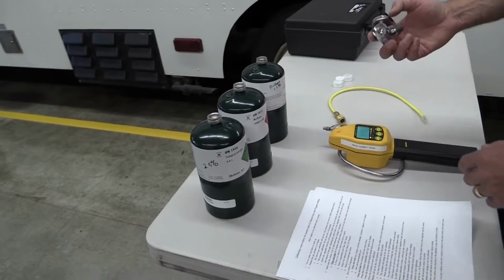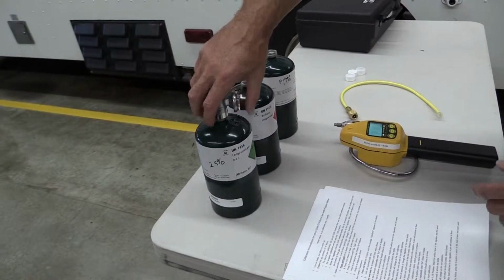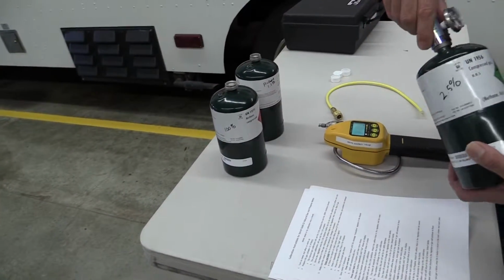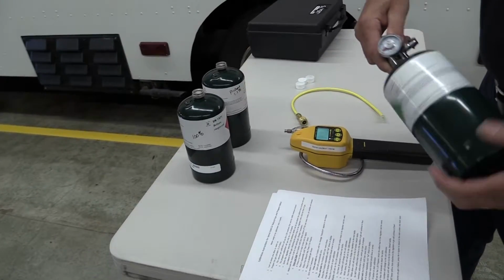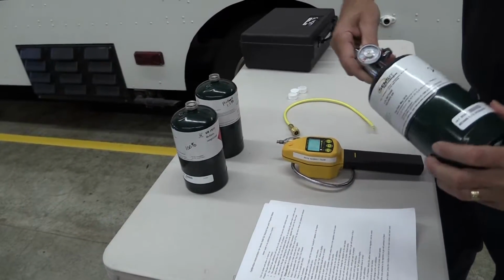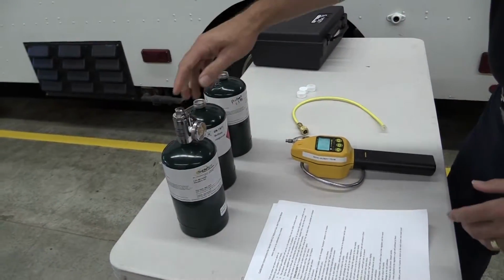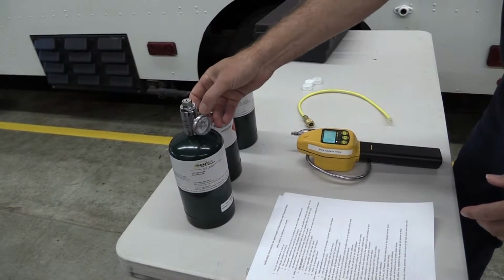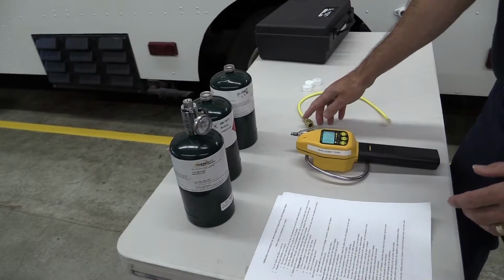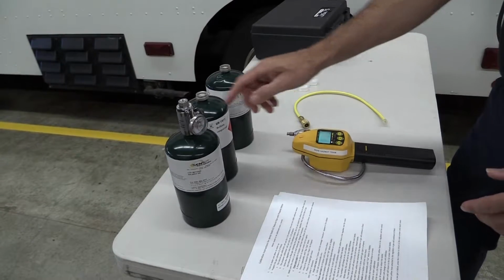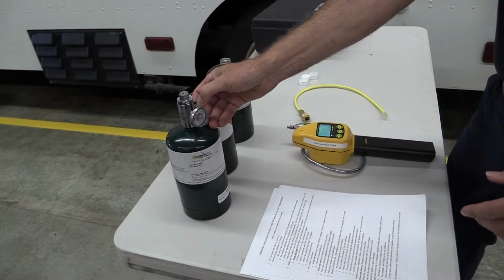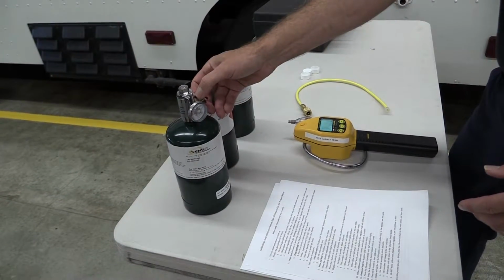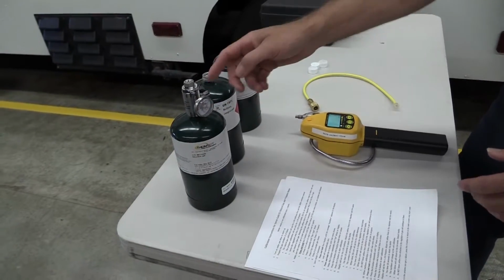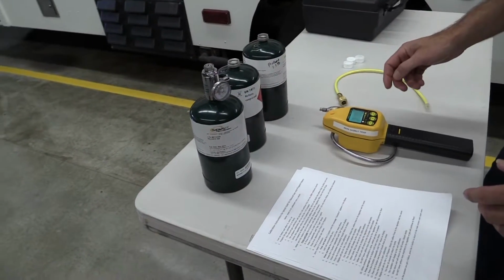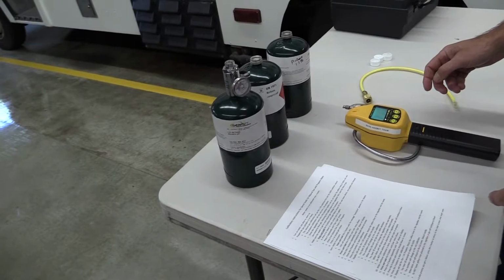We're going to start in natural gas mode, and so the first gas that we'll need is the 2.5% natural gas or methane solution. Put the regulator onto the gas bottle, but don't hook up the yellow hose yet. Once this yellow hose is hooked up to the port, it will start flowing gas. So you don't want to leave it hooked up at any point when you're not looking to flow the gas.